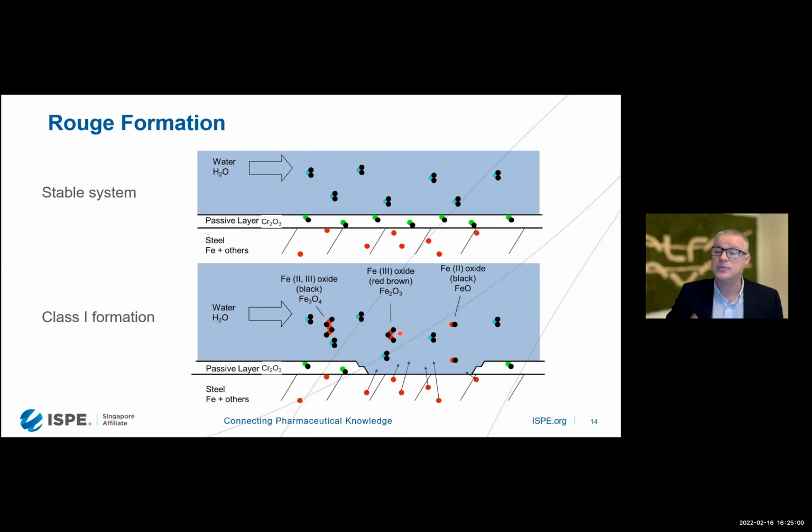And when it comes to turbulent areas, it will be smashed onto the surface and get deposited on the surface. It is also that plastic materials, PTFE in the diaphragm, EPDM in the diaphragm or in the gaskets, will also, nearly like a magnet, suck in this ferric oxide onto the surface.